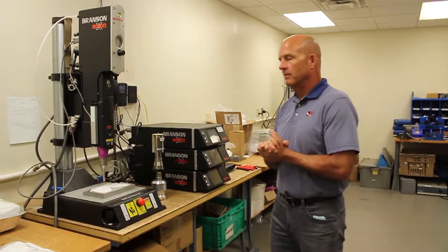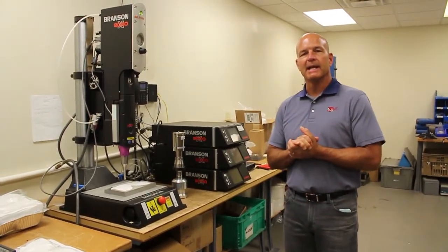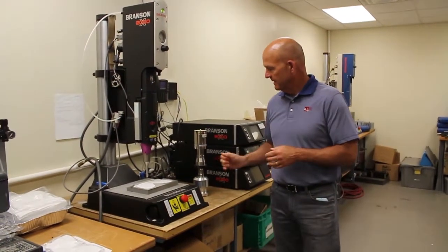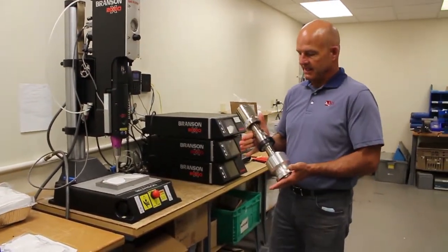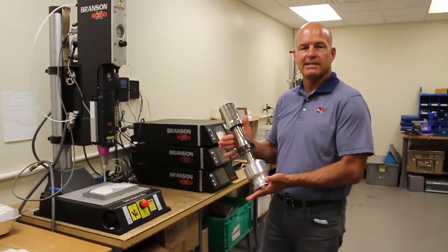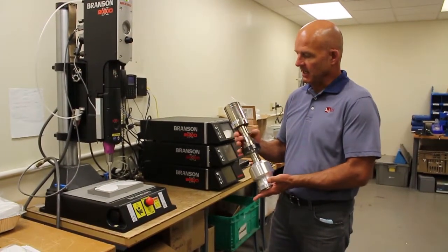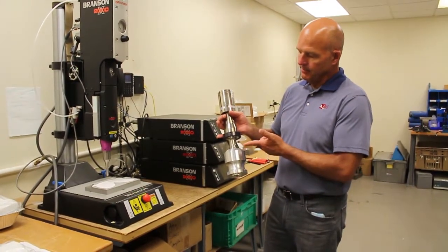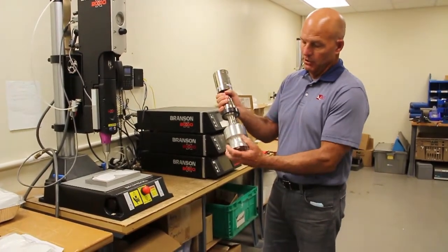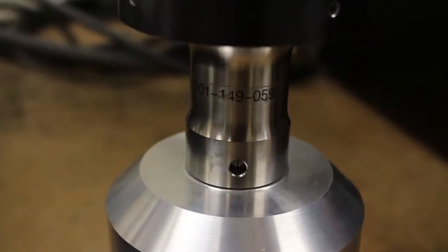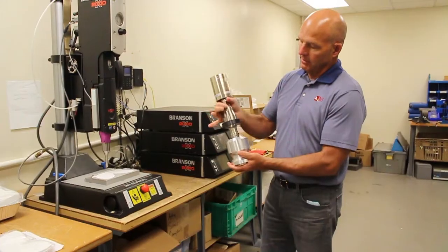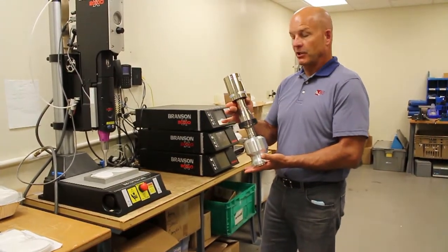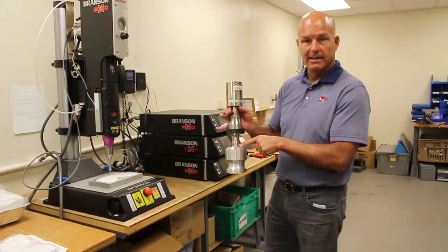So first of all, there are two types of overload conditions in ultrasonic welding. The first type of overload is an overload that occurs in the first 50 milliseconds, 50 to 100 milliseconds. And that typically is something wrong with the stack assembly, similar to the last video we shot. The converter, booster, horn, and typically it's something where the stack has come loose, a component is loose, the horn is loose from the booster, or the converter is loose from the top of the booster. It could be a cracked stud at the interface.